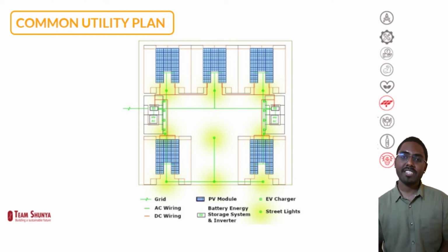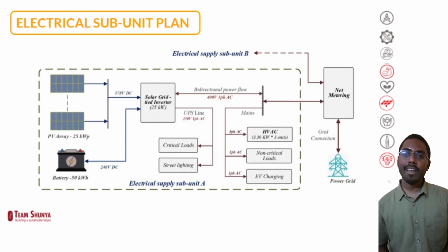PV panels are placed individually on each house and electricity is supplied from the common utility room. We are using REC panels which occupy less space and give high efficiency. The overall electrical supply system is divided into two subunits. The single line diagram of one of the subunits consists of 25 kW of PV, 50 kWh of battery and 25 kW of inverter.